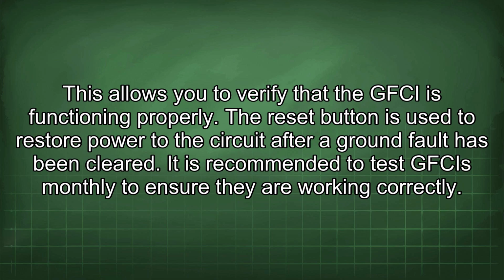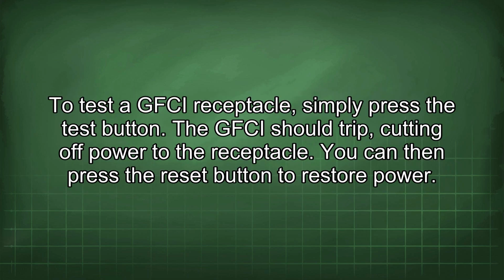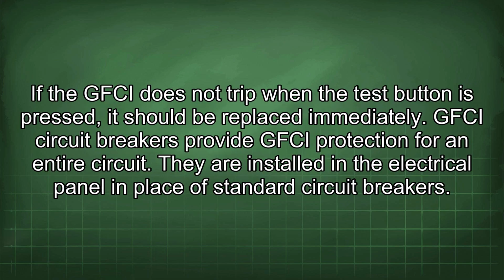It is recommended to test GFCIs monthly to ensure they are working correctly. To test a GFCI receptacle, simply press the test button. The GFCI should trip, cutting off power to the receptacle. You can then press the reset button to restore power. If the GFCI does not trip when the test button is pressed, it should be replaced immediately.